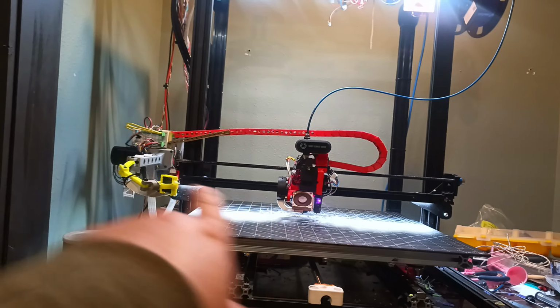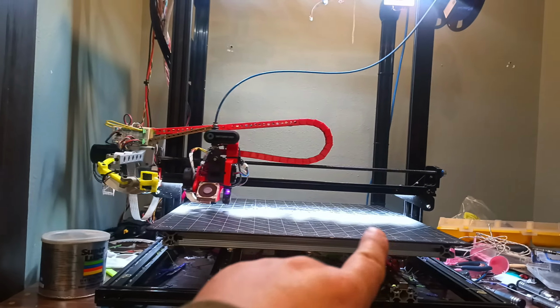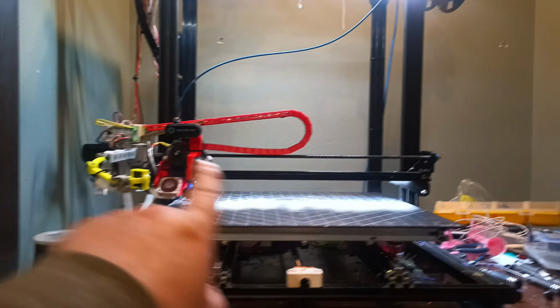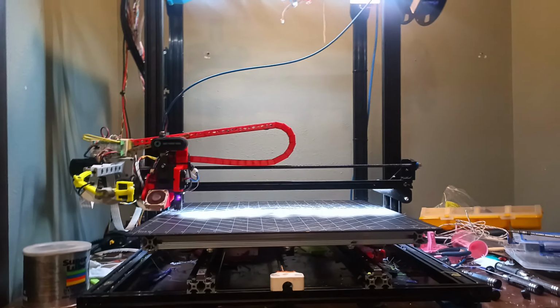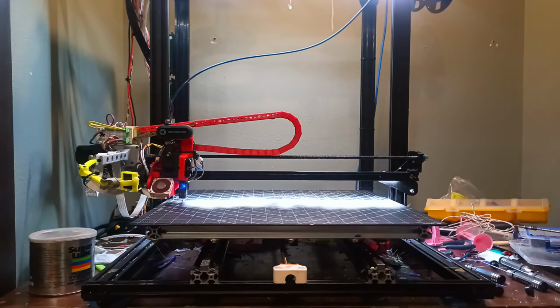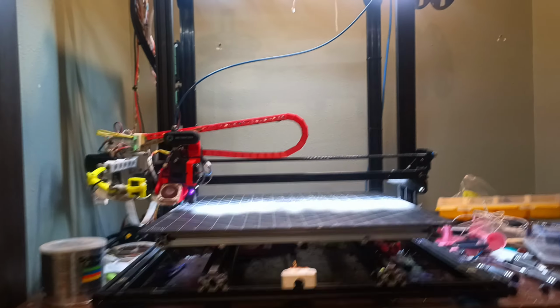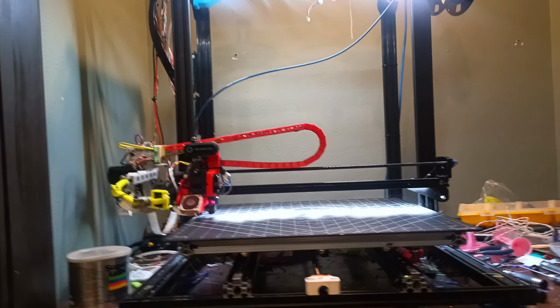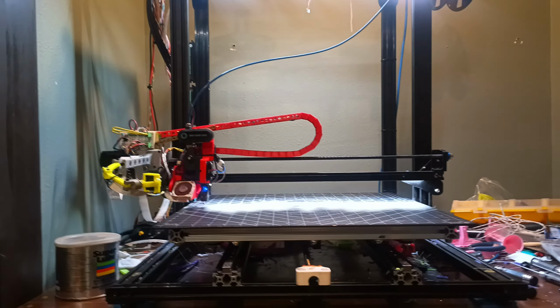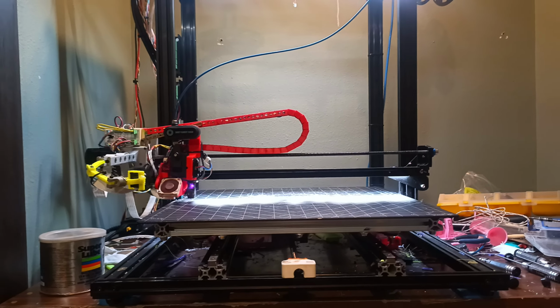All right, I found 0.07 millimeters is the difference side to side, and this side is 0.07 lower than that side. So what it's doing now is moving this side up and then double checking to make sure they match. Its goal is 0.02 millimeters, that's what it'll settle for, but it always tries for 0.01 or 0.00. So we'll see what it actually gets to here.